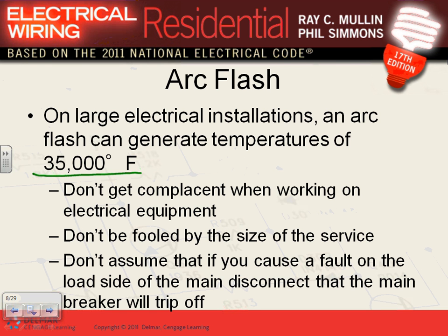Because if you've ever seen a category 4 piece of PPE, protective gear - your productivity, Chris, I don't know about you, if you put it on, your productivity is cut down to a quarter. Imagine in the middle of summer when it's hot and you're working on a piece of equipment with that shield trying to be productive. Your productivity is 25% of what it should be if you're dressed up like this. You just can't move in it. So you limit dressing up like this to only when you have to, only when you need to.